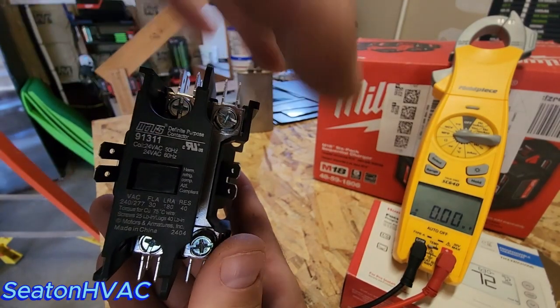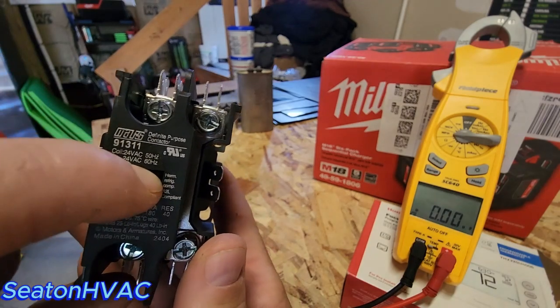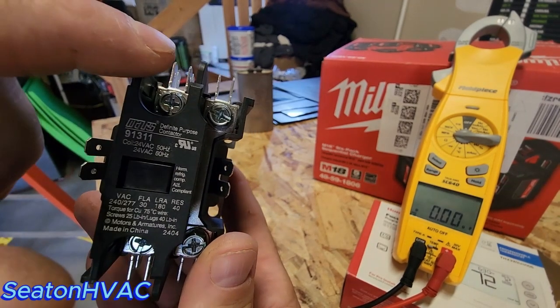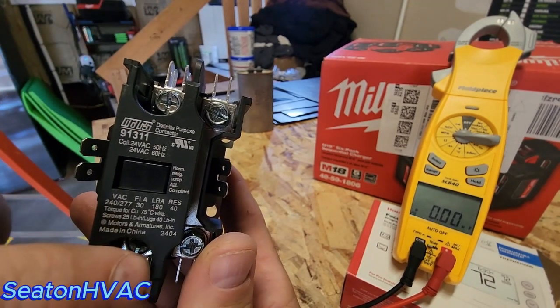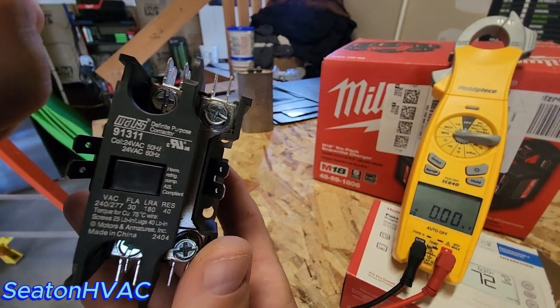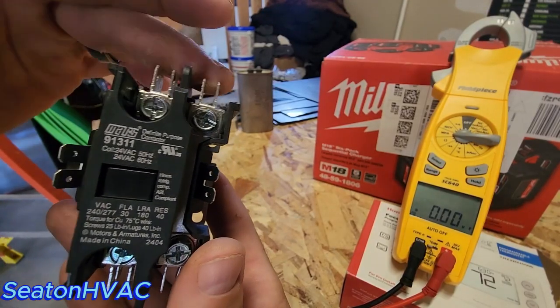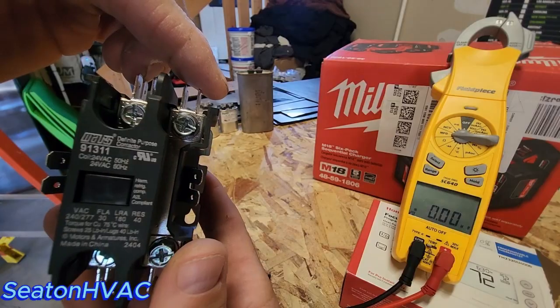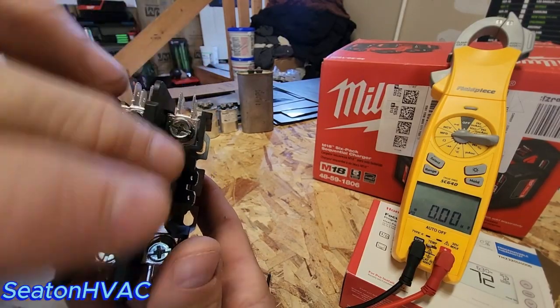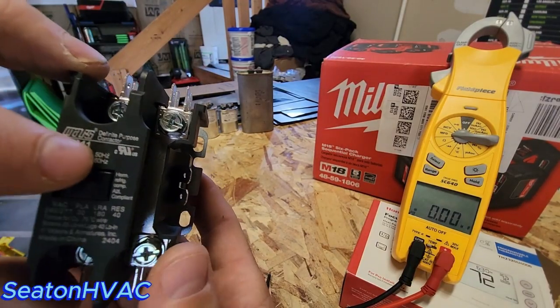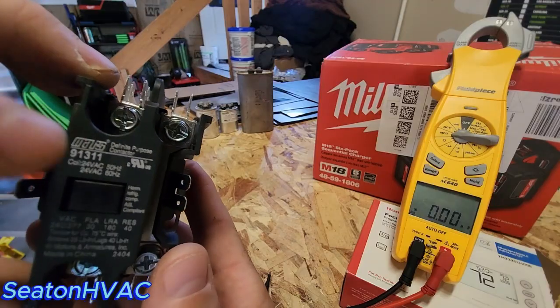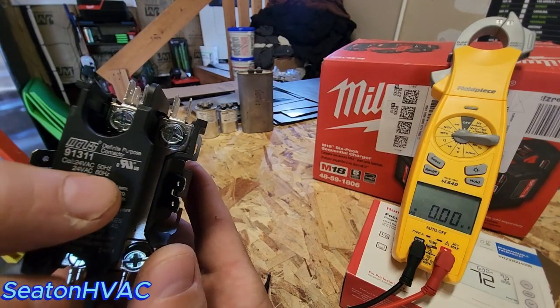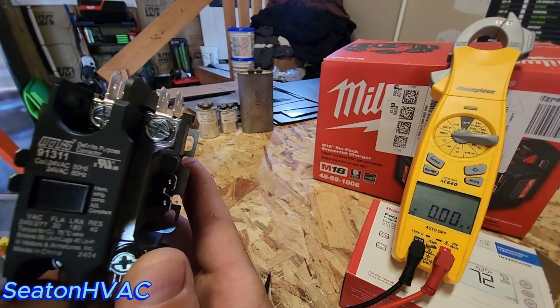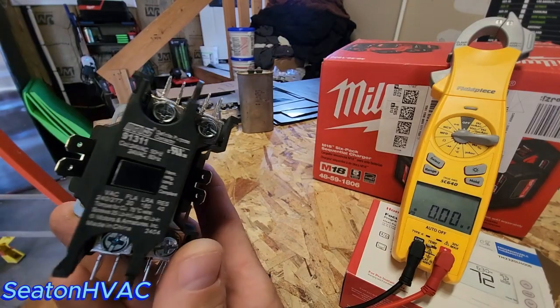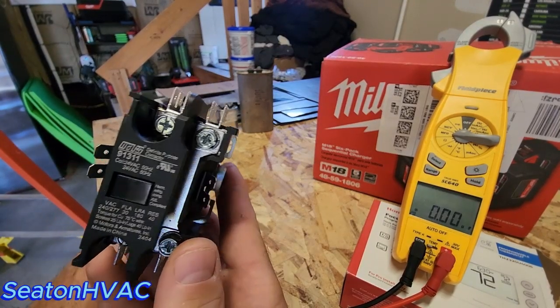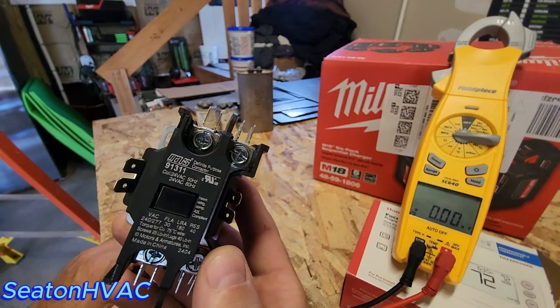So when this energizes the coil, it pulls this in, and that allows your 120 volts to flow to the top here, and that'll energize your equipment, because now you have 240 volts coming out instead of just the 120 that's always there. If this was a 2-pole contactor, these would both be interrupted per the switch, per the button that pulls in. So that's the basics on that. Hopefully I explained it well. I'm not the best at explaining this stuff. I'm good at working on them.